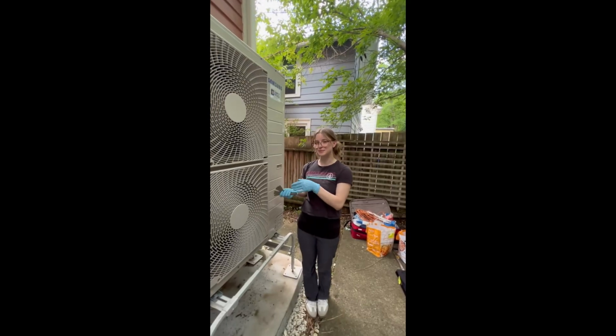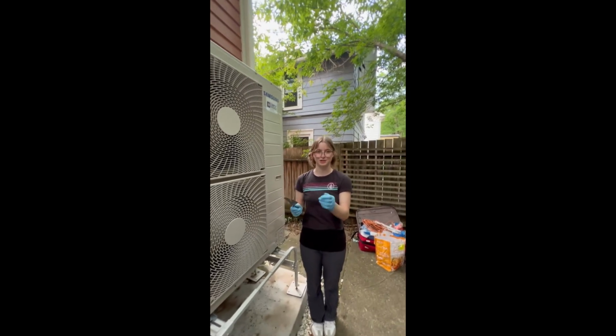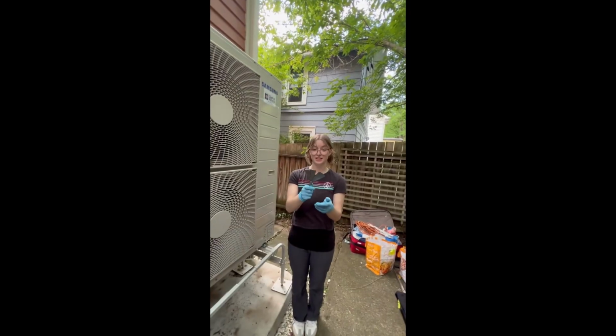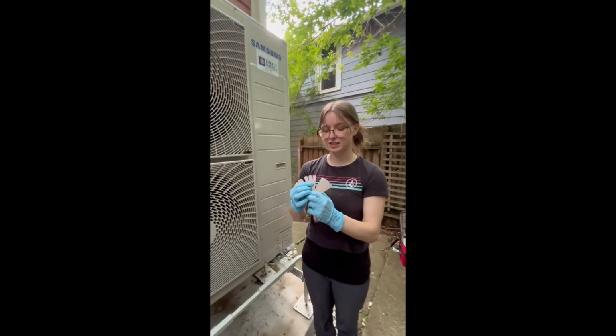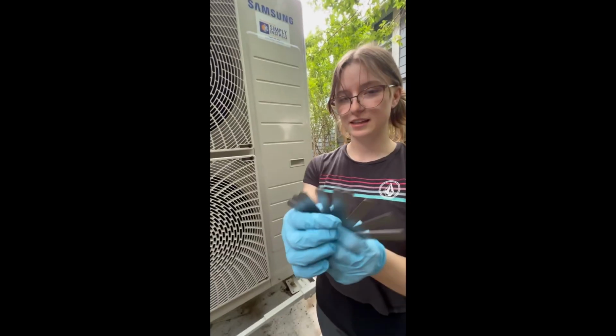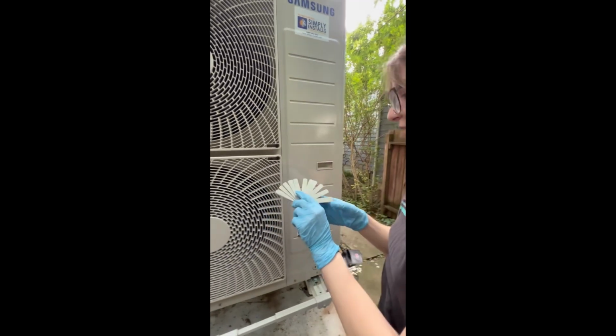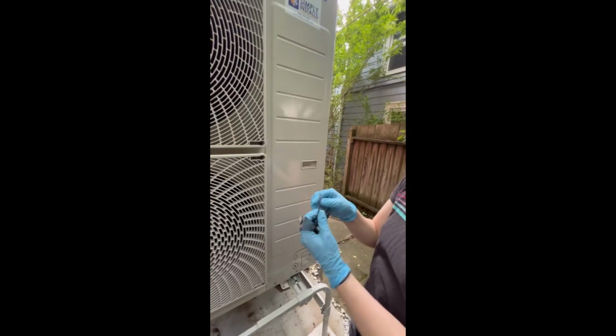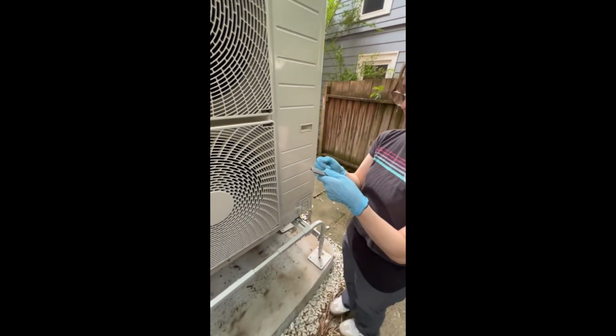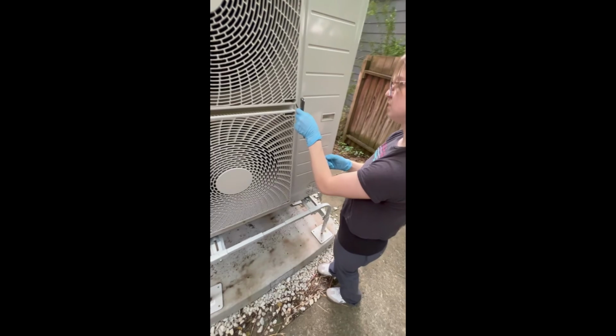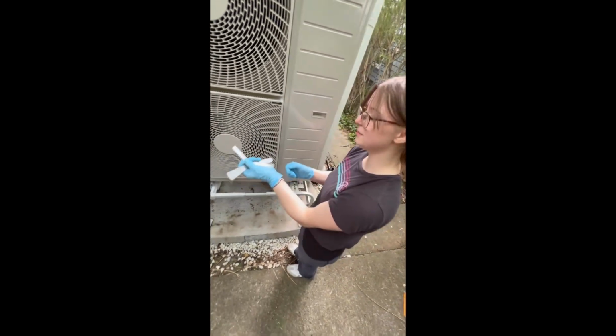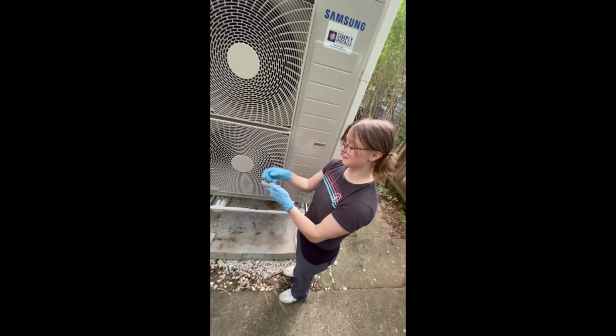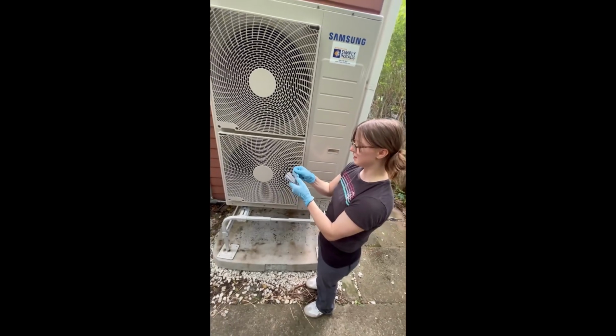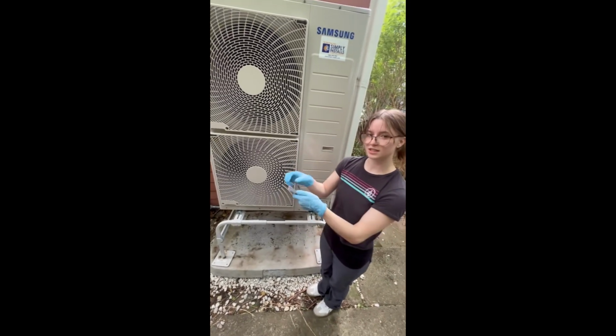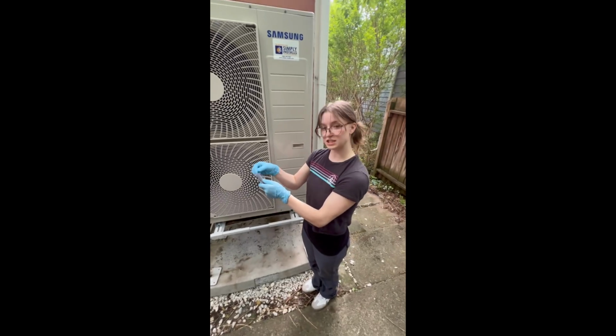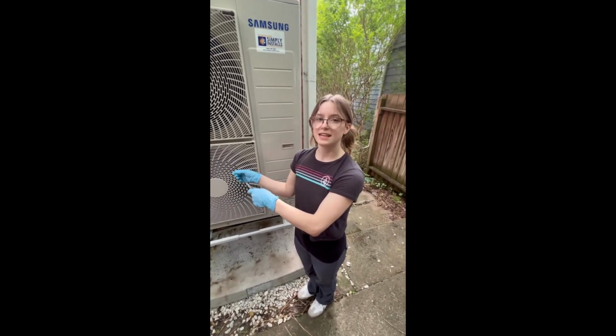There are lots of seams on these heat pumps which we can't exactly measure with a tape measure, so we use something called a feeler gauge, which is just metal sheets that differ in thickness and go in order. How you use it is you pick a width. This is 0.4 millimeters, and you pop it in the hole, and if it fits, it means that it's either that thickness or it's bigger than that. So then you go to the next size up, and you repeat until you are not able to fit the gauge in anymore, and then you go back down to the last size, and that's the size of your gap.